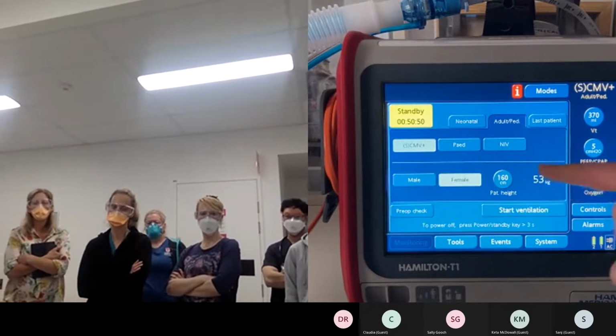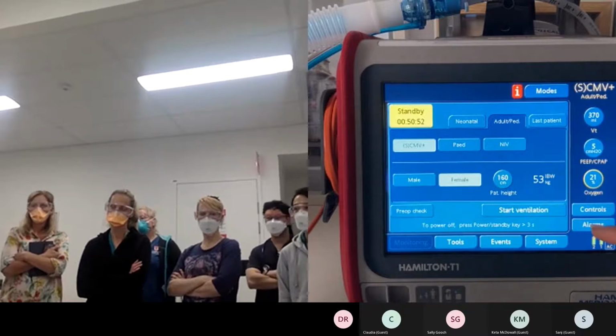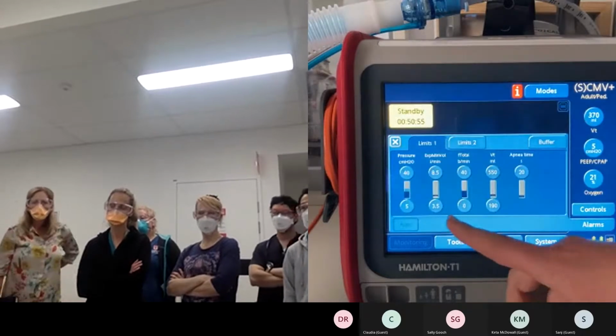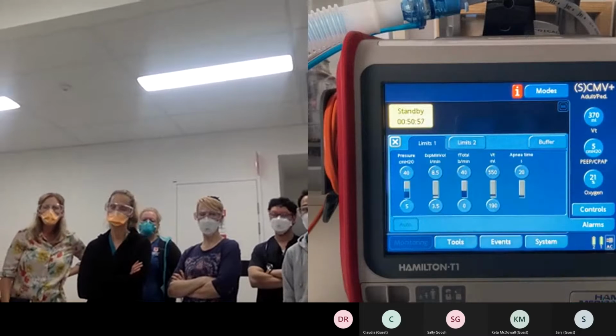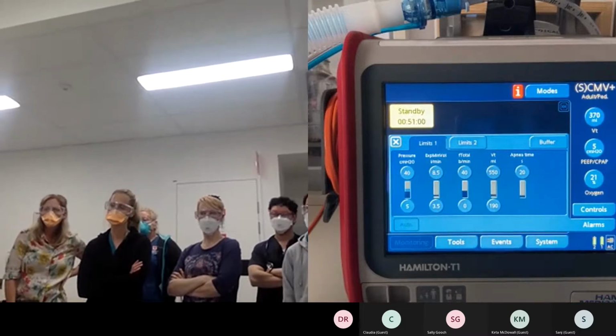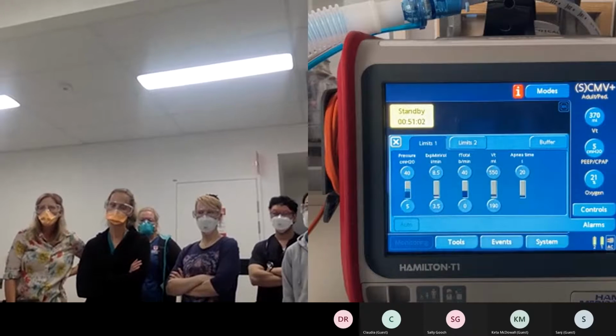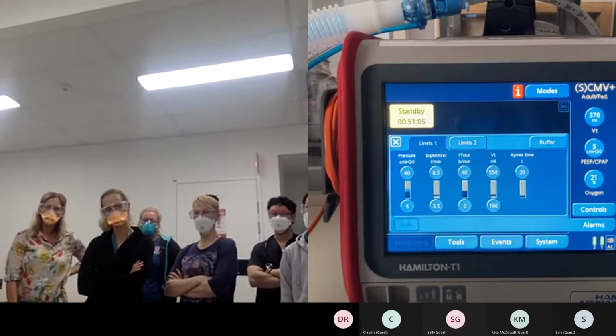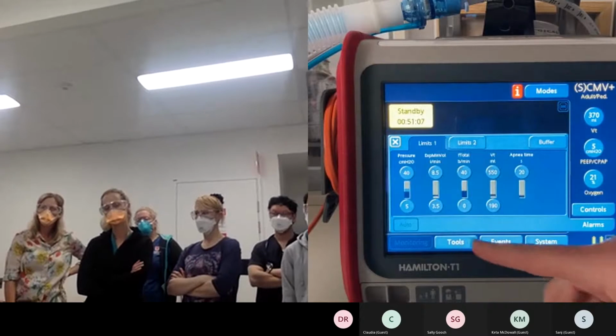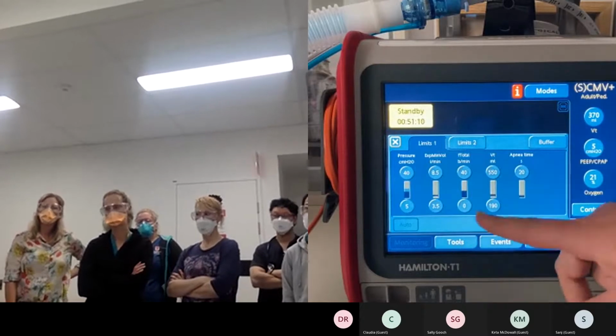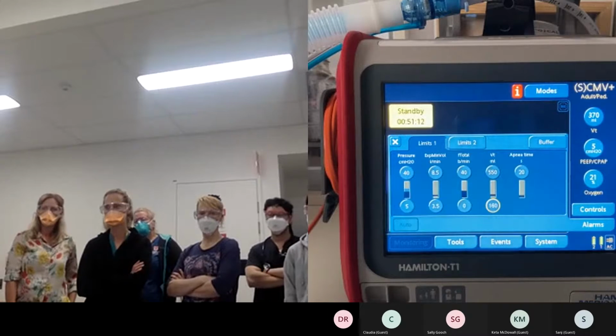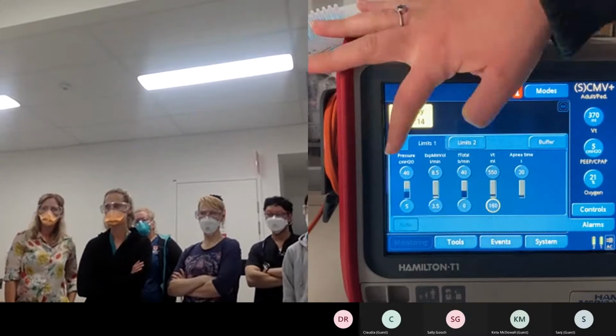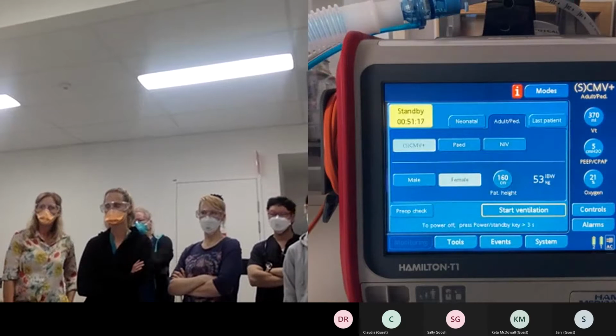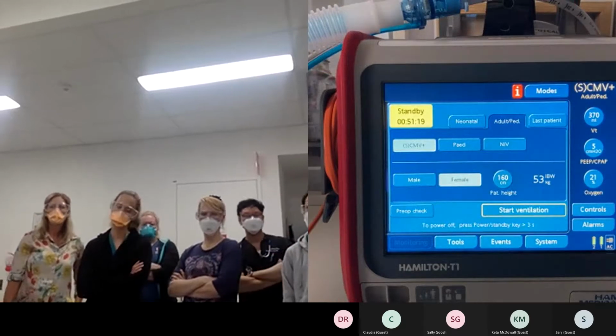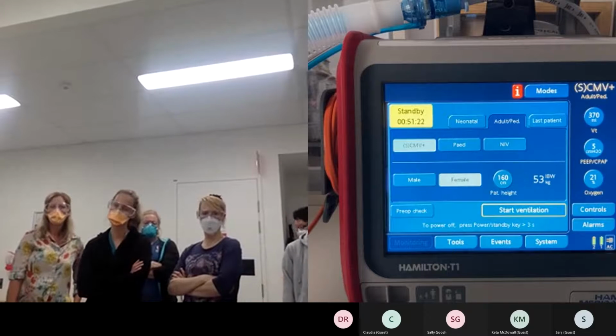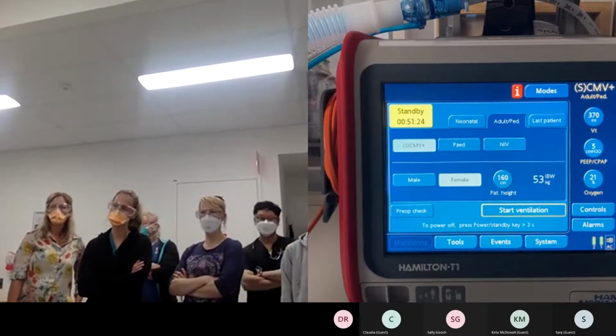What's happened with this 53 kilo ideal body weight is that if I come down to my alarms, the minute volume and tidal volume alarm limits have set around that as well. So the ventilator is always going to still work if you've forgotten to set that gender and height at the beginning, but you might get inappropriate alarm messages. Okay, so you would have to come in and adjust them independently. Okay. You need to confirm. You're up to where I'm up to. Yeah, we're good. Okay.